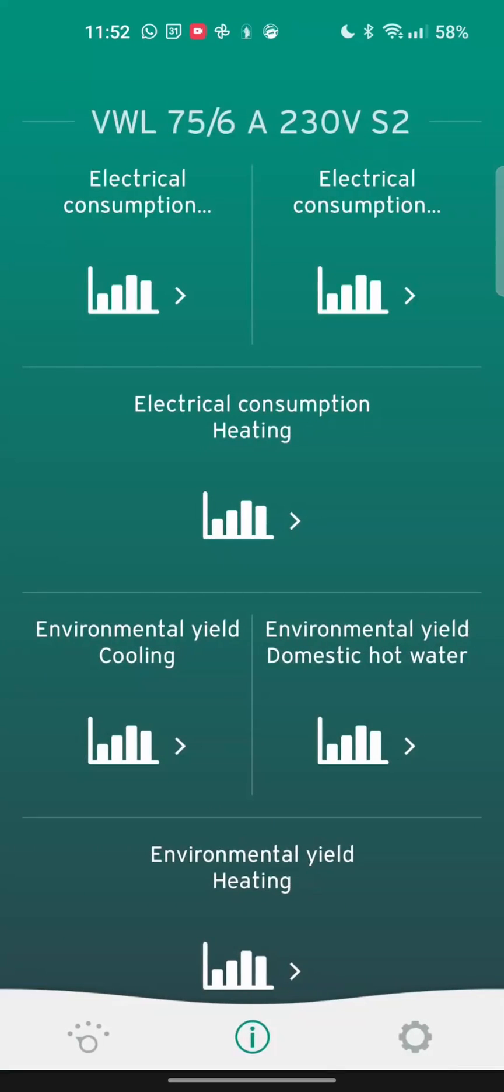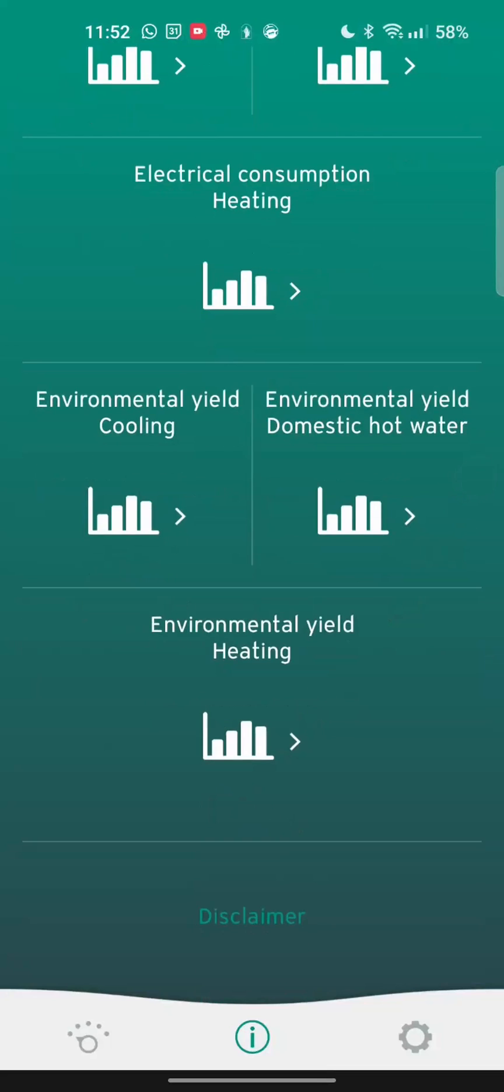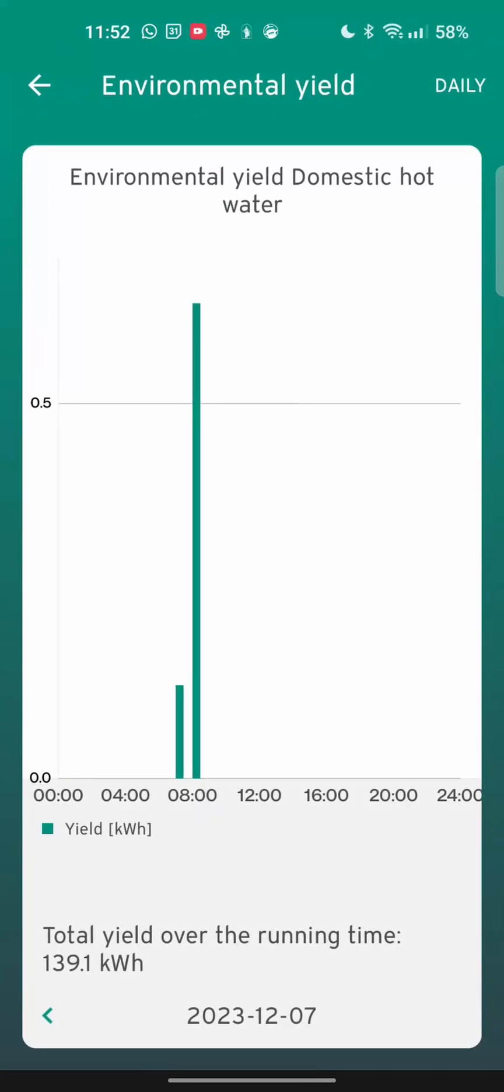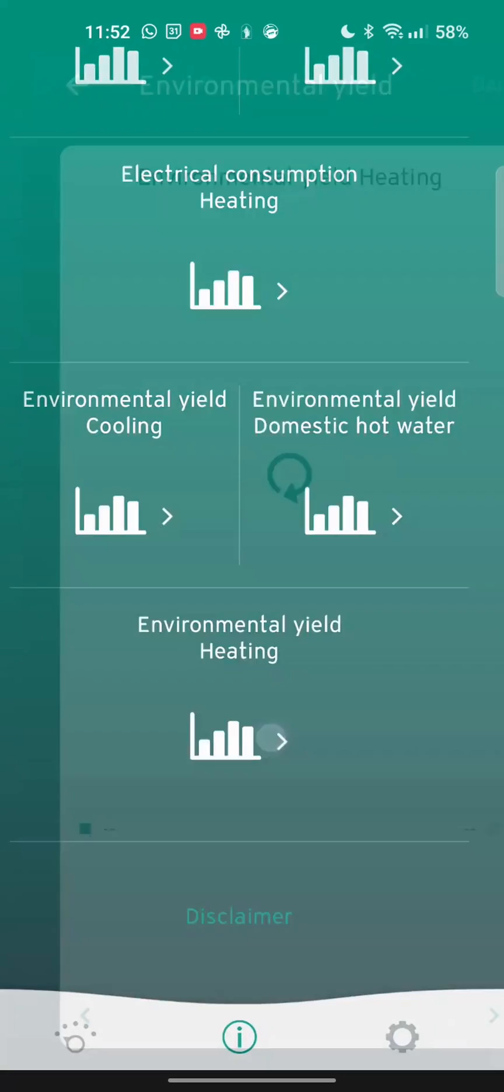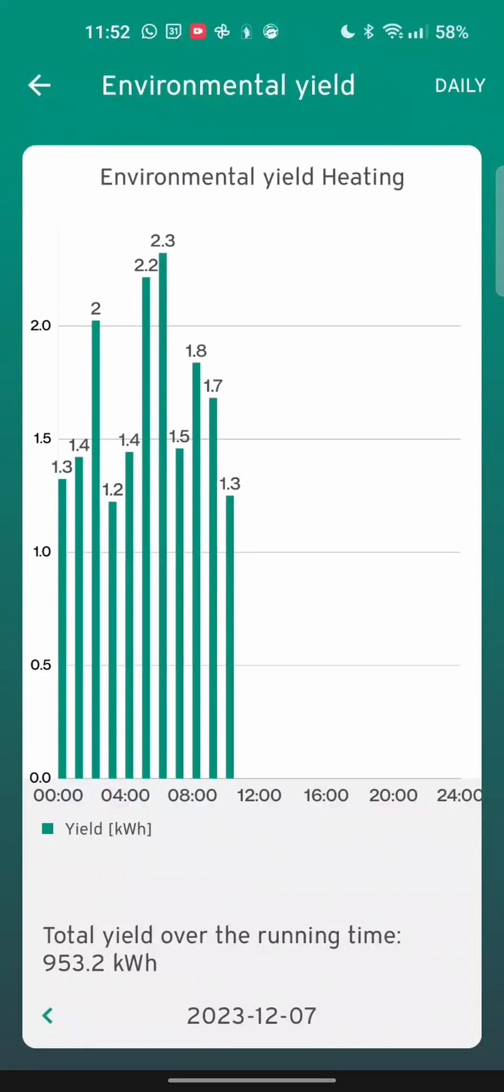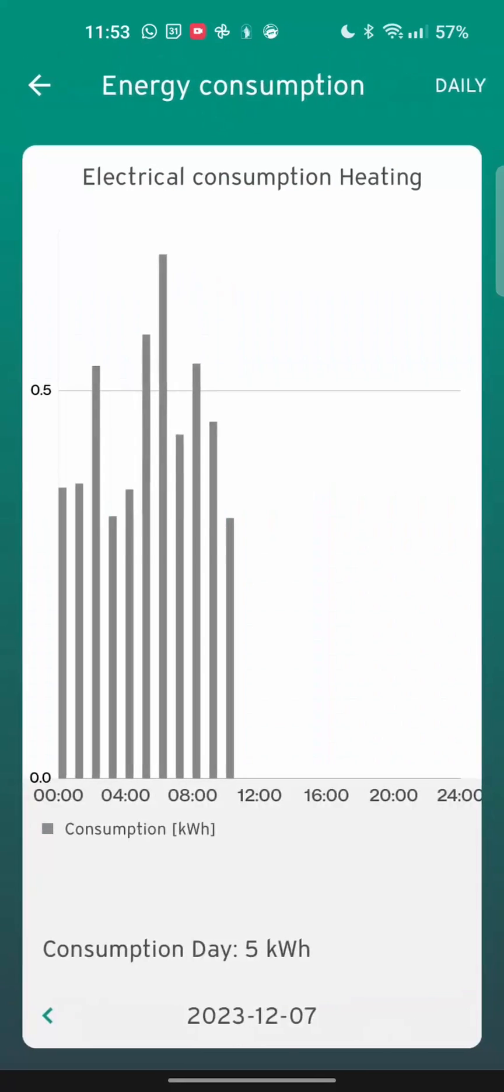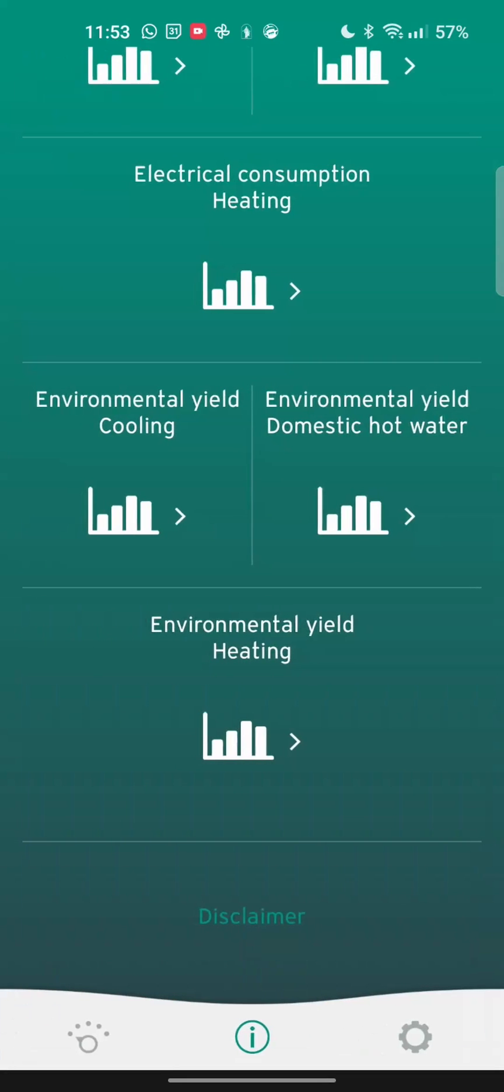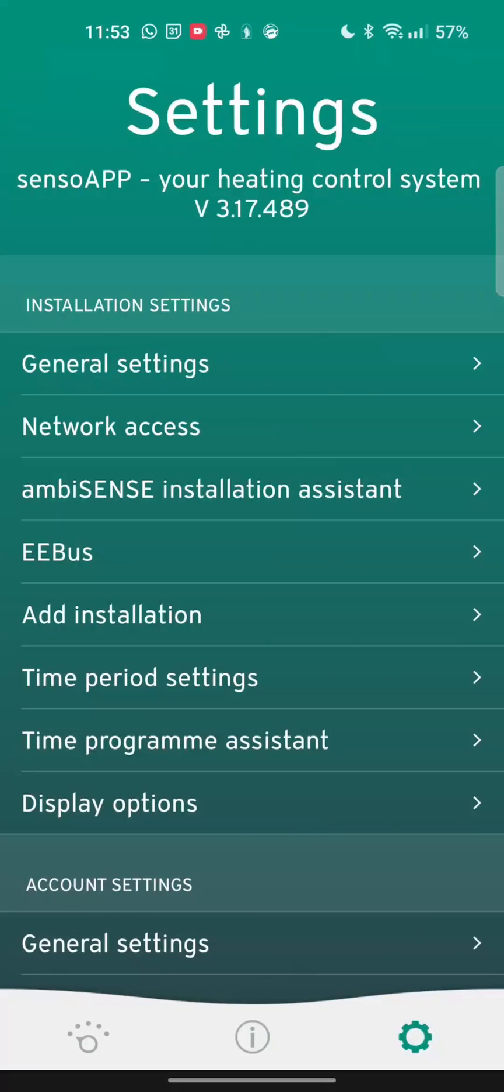You can basically do the same thing for the yield as well. The yield figure is not the total yield from the heat pump. It's not the energy that has been pumped into the house. The yield is the energy that has been collected from the outside air by the heat pump. If you want to combine this, you'll have to combine both the yield and the electrical heating consumption. And once you combine both those figures, that's how much heat you're putting into the house.